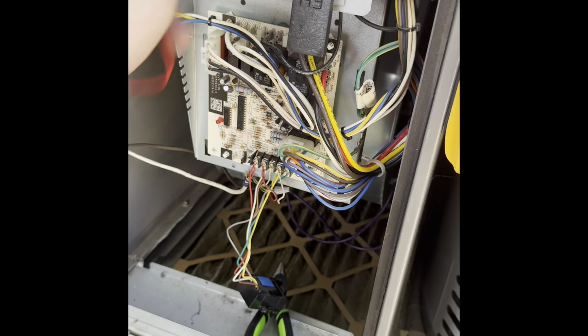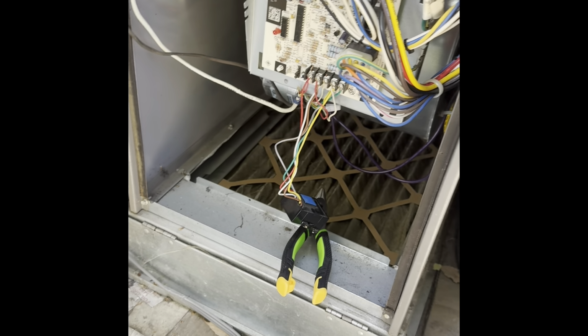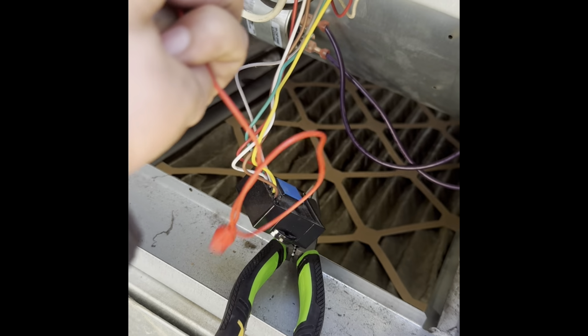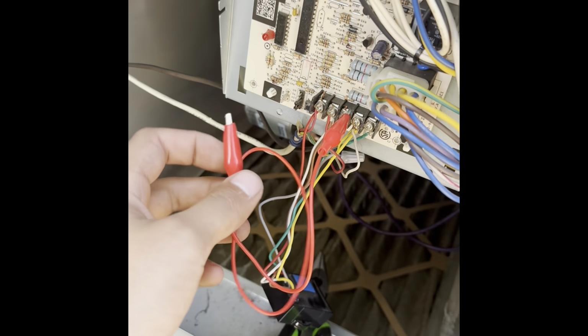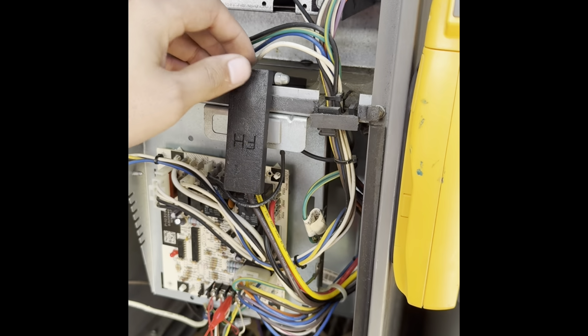So I'm going to push this in here, and we should be getting power as soon as I connect the system back onto the power. Okie dokie, so I see the LED light is on. So what we're going to do, we're going to jump W. I always like to connect the Y one first, due to the fact that if I connect it to the red, and for some reason this end touches something, it can create a short. So that's the reason why. Okay, it should be staying on.